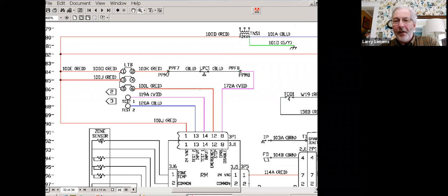All right, I said earlier, and I just want to point this out, we feed the board from 2 or 3 different places. So just because the light is on the board doesn't mean we can't be in a cool fail, we can't be in a locked out situation. But if you look at this, 24 volts comes directly off the transformer for the control side of the system, and then it tees off, and this I believe goes over to the phase monitor.